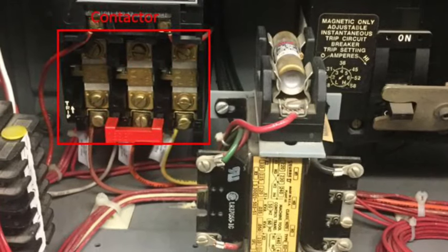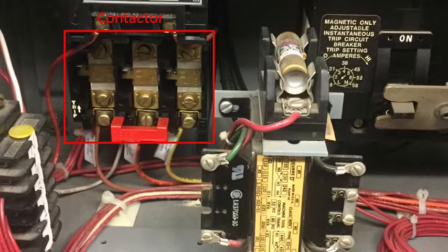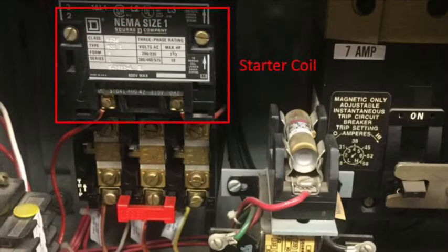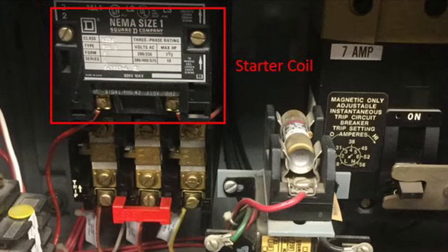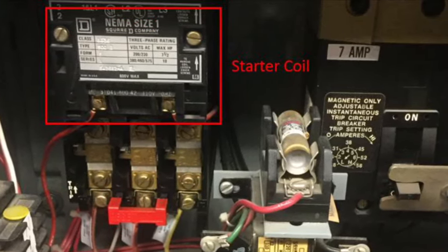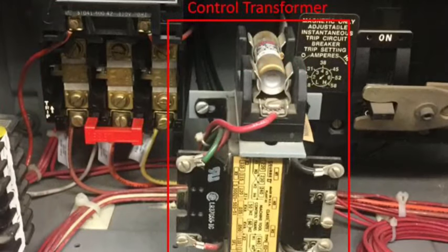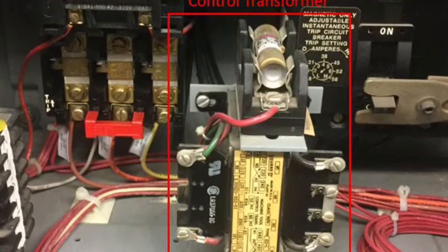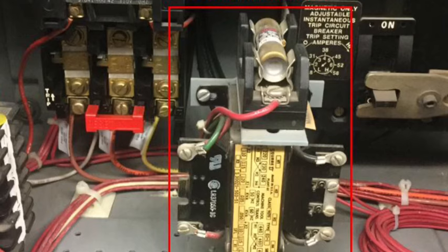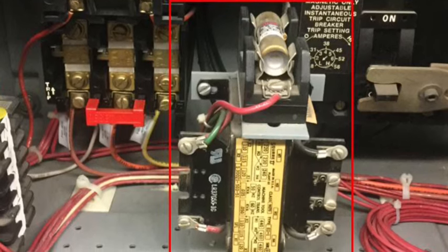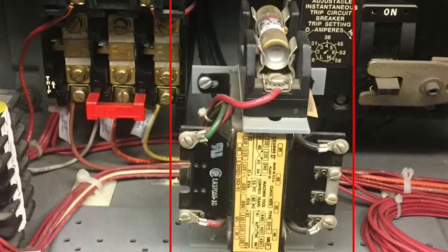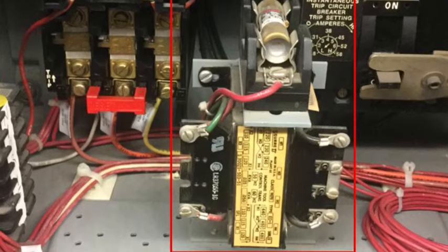The motor contactor connects the high voltage to the equipment being energized. The contactor coil is the electromechanical device that engages the high voltage contacts. The control transformer takes the line voltage of the starter and reduces it to its manageable low-level voltage for control purposes. The fuse protects the transformer from the overcurrent conditions.